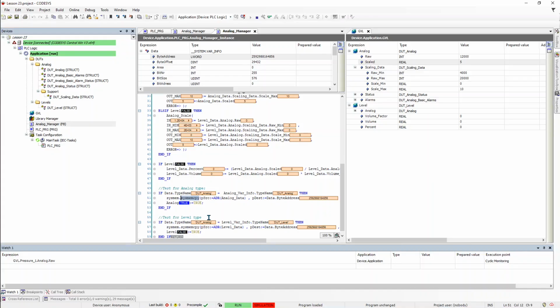And then we do exactly the same with the control method, where we detect the control method type, so whether it's a PID structure or an external request, which would just be a structure with a single variable in, we can still detect that structure type and say, okay, it's being controlled this way. And suddenly you have a function block that is capable of controlling any drive that you use in your system, irrespective of its hardware or the control methods that are required later on.